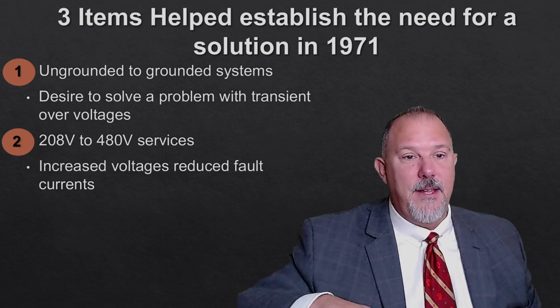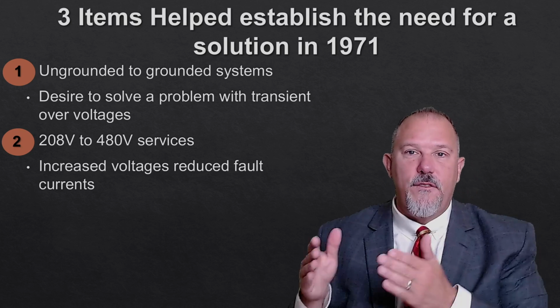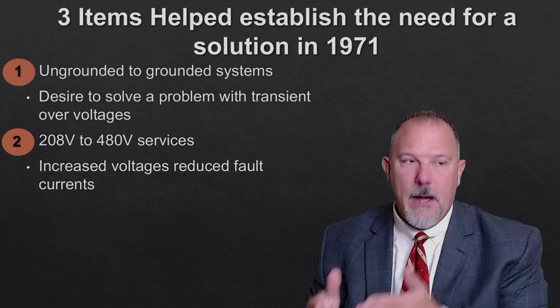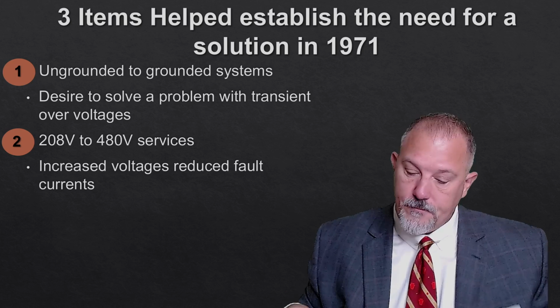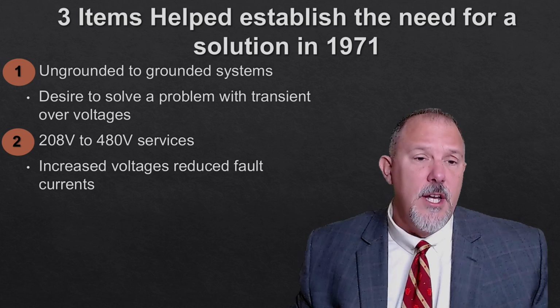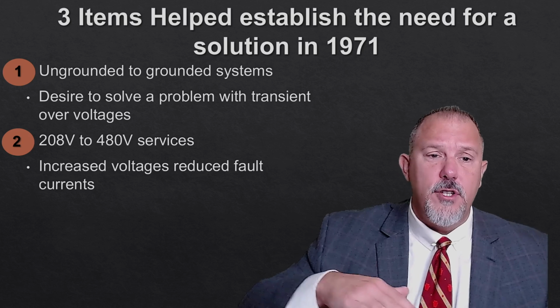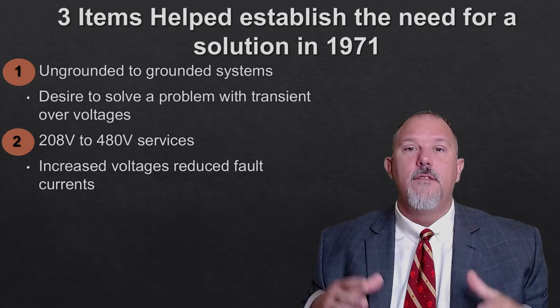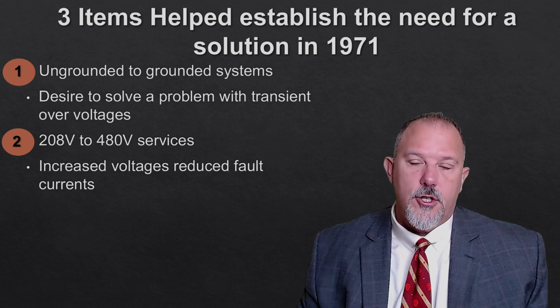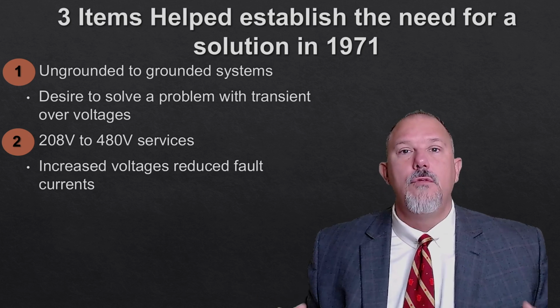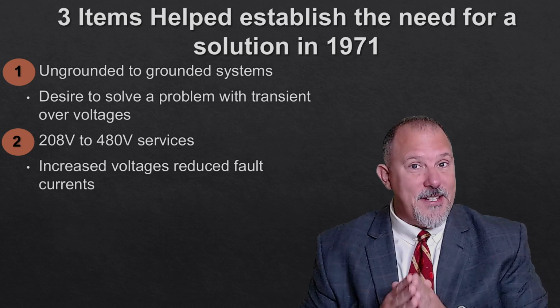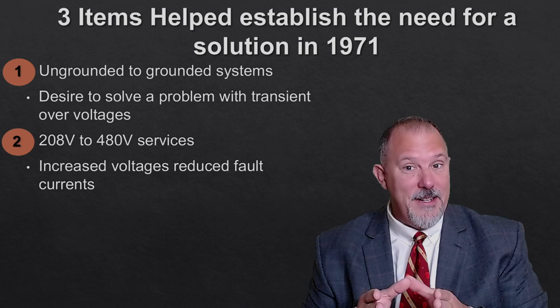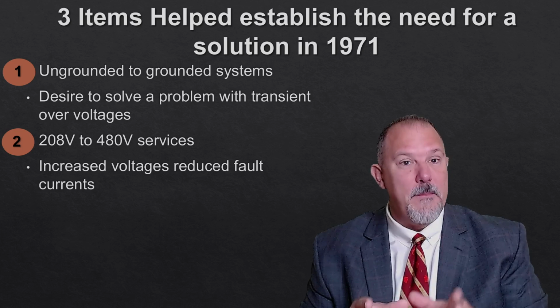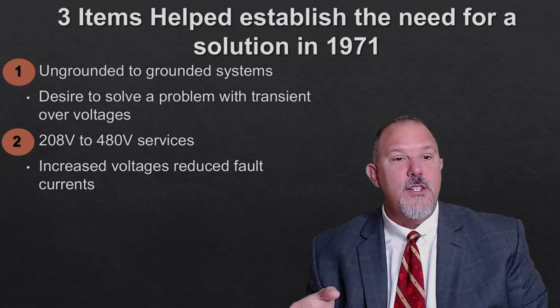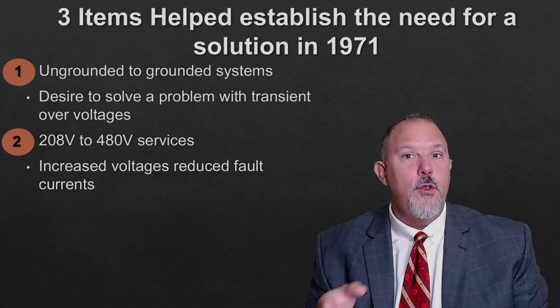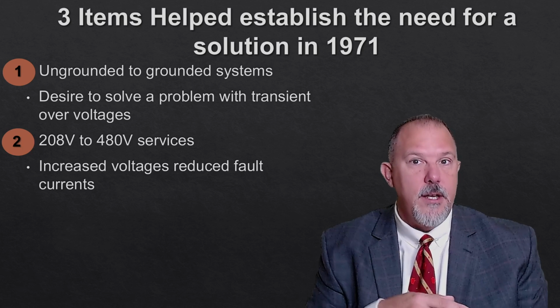Now, the second thing was they moved from 208 volts to 480 volt systems. Now, what did that do? Well, moving to a higher voltage. What is voltage? Voltage is pressure. So a higher voltage can give you more arcing current, which is not necessarily a bad thing, right? Because it's all about the clearing time. But I'm just saying these lower voltages will give you lower arcing currents.